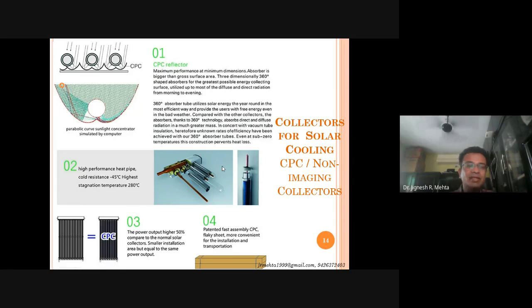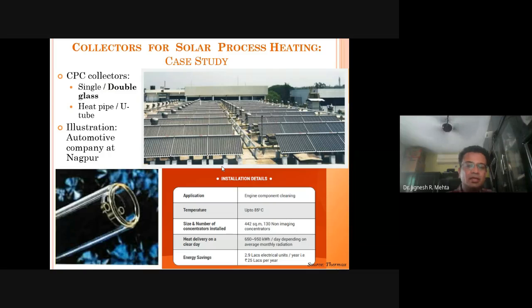So this explained to you the details about the CPC evacuated tube type of collector with heat pipes. And there is another arrangement also possible, as shown in this, where you can have a U tube. In this case the water is going to enter through one of the tubes, go to the opposite end and come back. But again, you cannot just put the tube inside this evacuated tube, right? You have to provide fins. I think the fins are also seen in this, which conduct the heat from the inner surface of the inner tube to these tubes, and as the water passes through these tubes, it gets heated. So this is another arrangement, the U-tube arrangement, in the case of evacuated tube collectors.